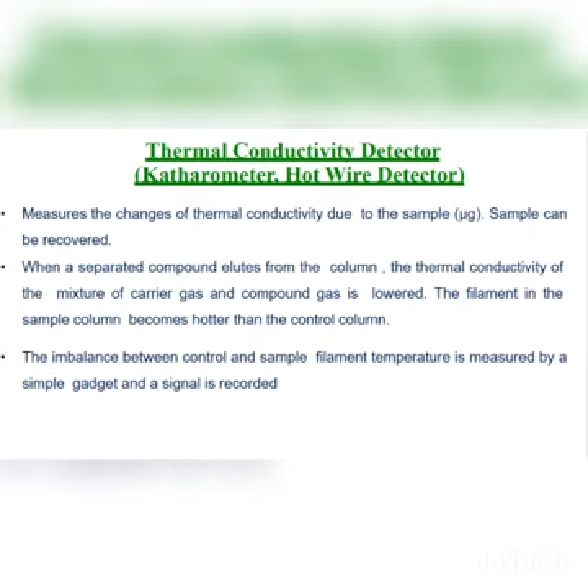When the separated compound elutes from the column, the thermal conductivity of the mixture of carrier gas and compound gas is lower. The filament in the sample column becomes hotter than the control column. The imbalance between control and sample filament temperature is measured by a simple gadget and a signal is recorded.